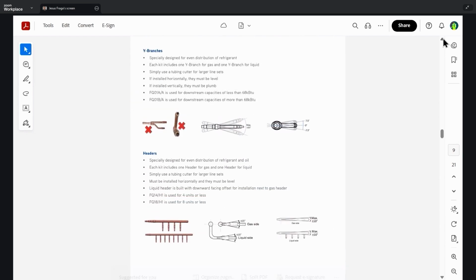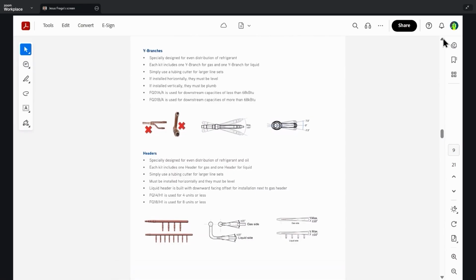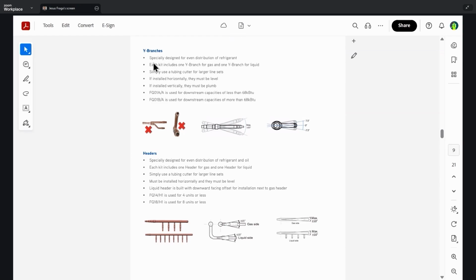Moving on. Y branch and header installation. This is very important when it comes to installation to avoid things like compressor failures, inadequate cooling, and increased energy consumption. These installations of the Y branches and the headers are crucial. So as we know, they're specifically designed for even distribution of refrigerant. Each kit includes one Y branch for gas and one Y branch for liquid. Simply use a tubing cutter for larger line sets. If installed horizontally, they must be level. If installed vertically, they must be plumb.